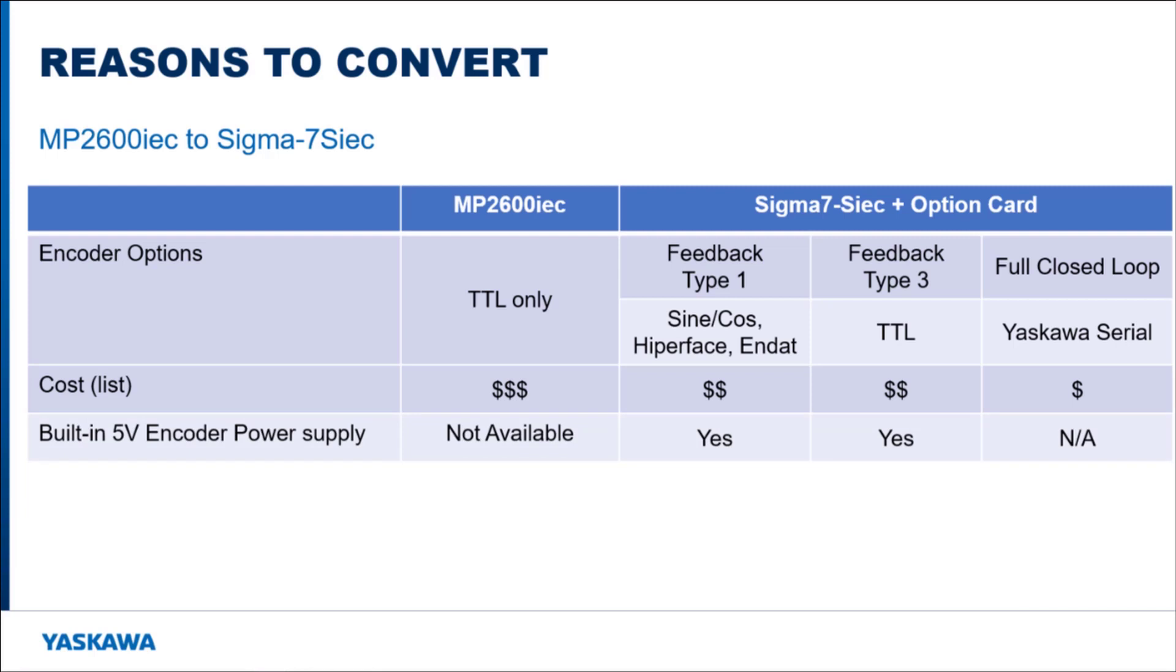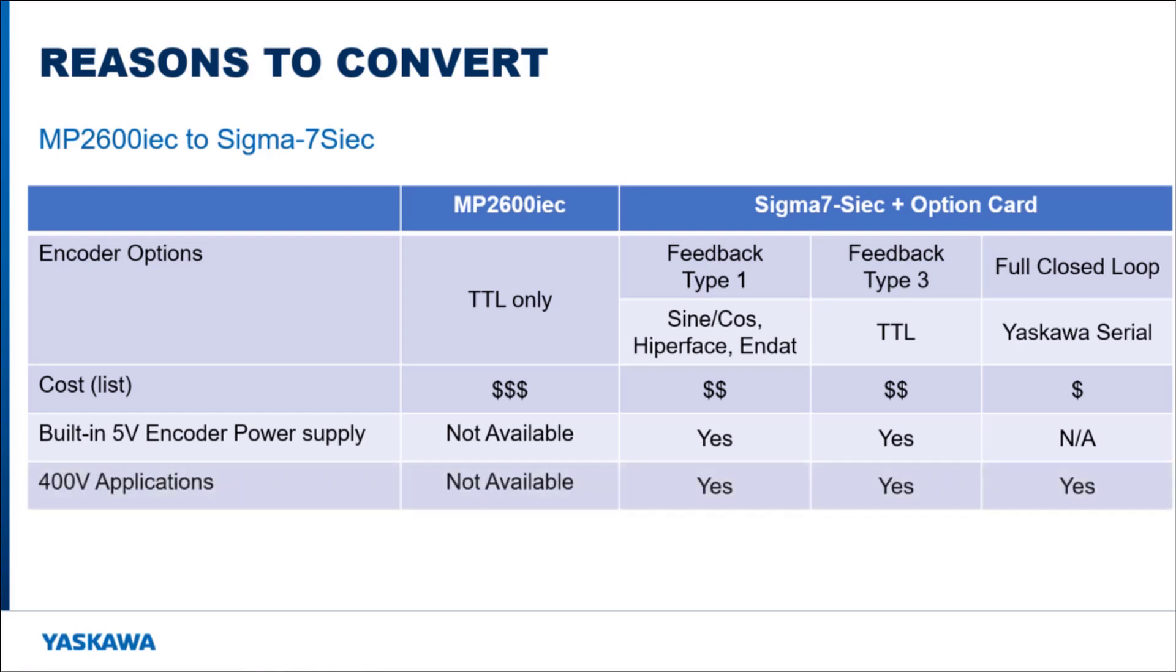The feedback and full closed loop option cards provide power for the encoder, so no external power supply is required. These dual feedback applications can also be converted to run on 400 volt systems, because the MP2600 IEC option card is not available for Sigma 7 400 volt servo amplifiers.